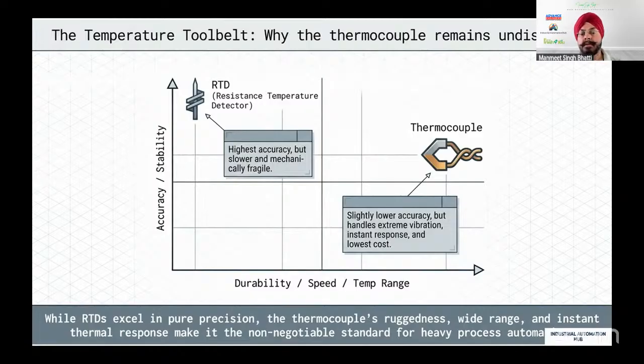On the other hand, we have thermocouples, which do not have very good accuracy compared to RTDs, but they are extremely successful in any kind of vibration, any kind of high thermal jumps, and they are quite rugged. They have a big range. So that is the way. It's up to you how you want to install or where you want to install.